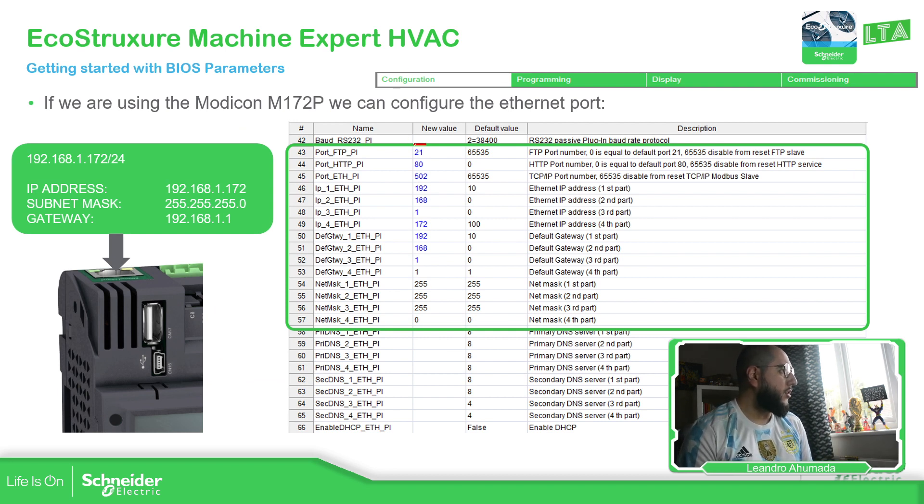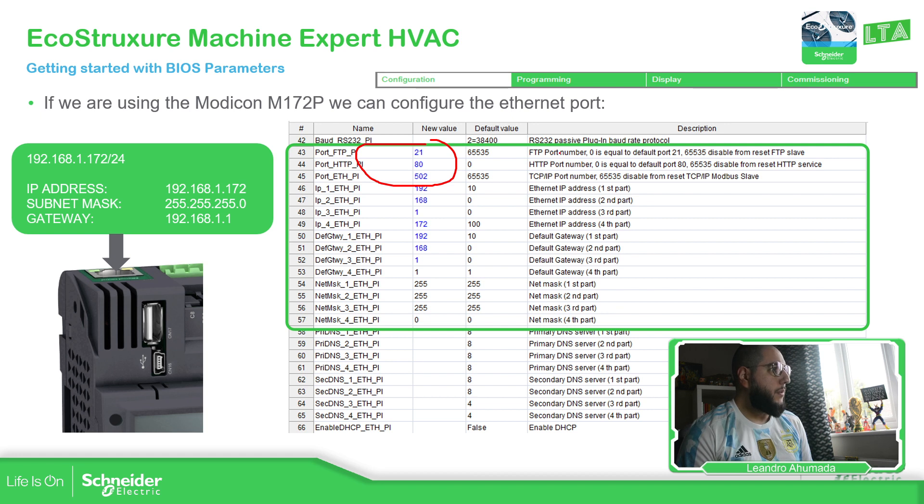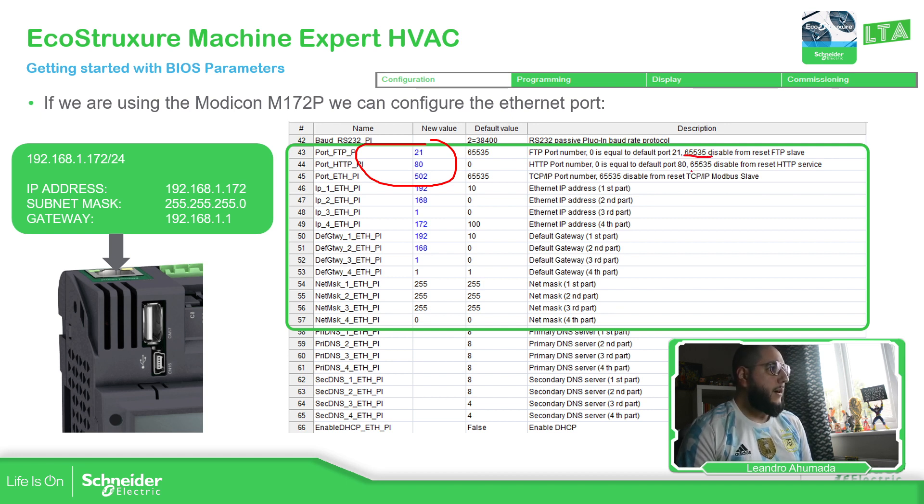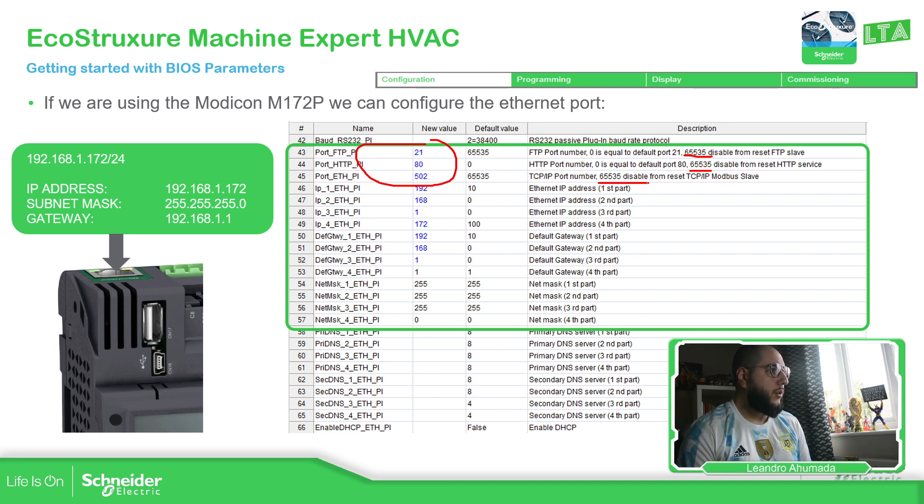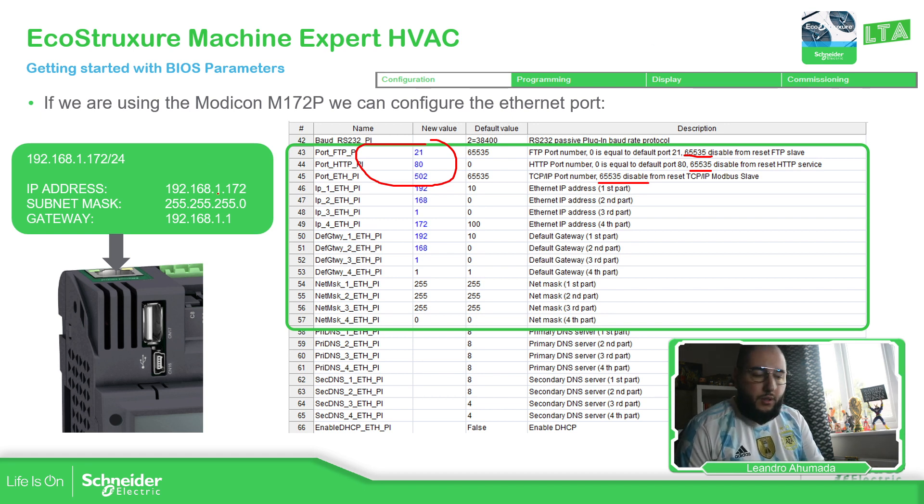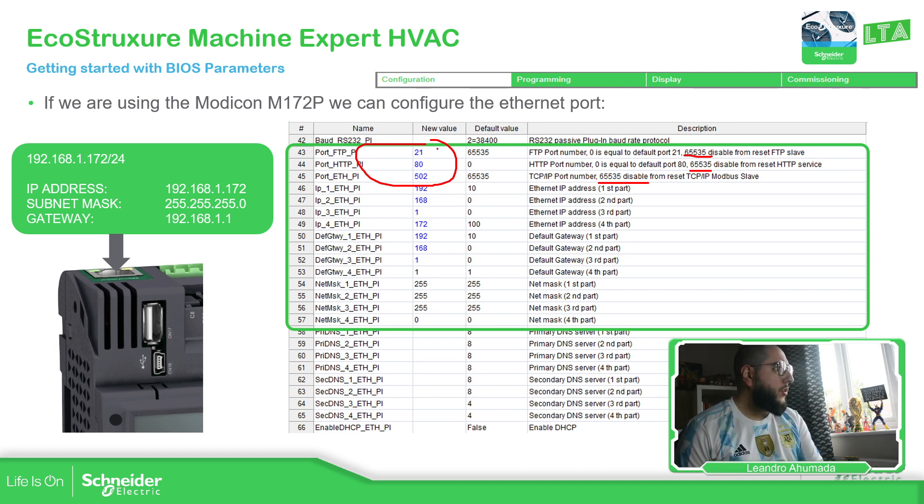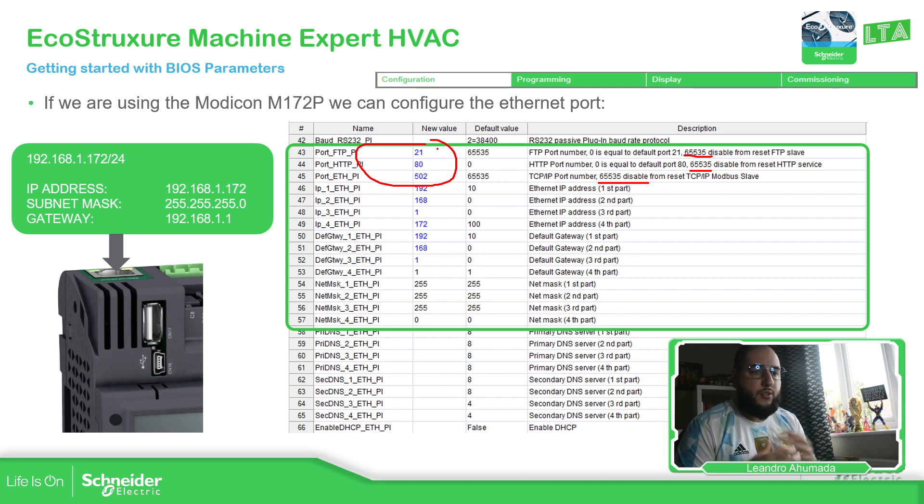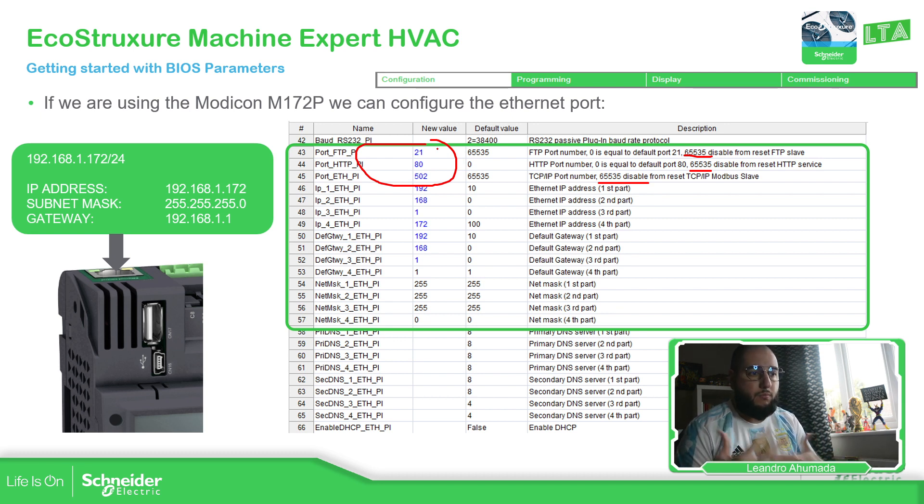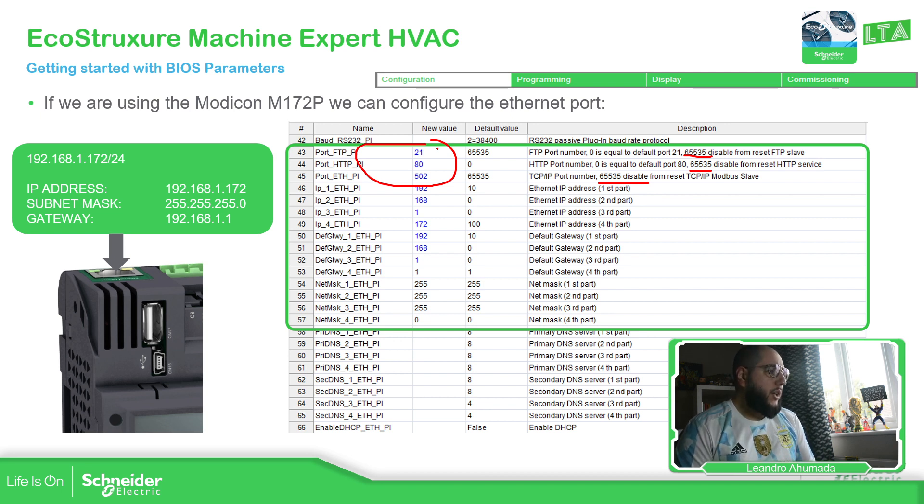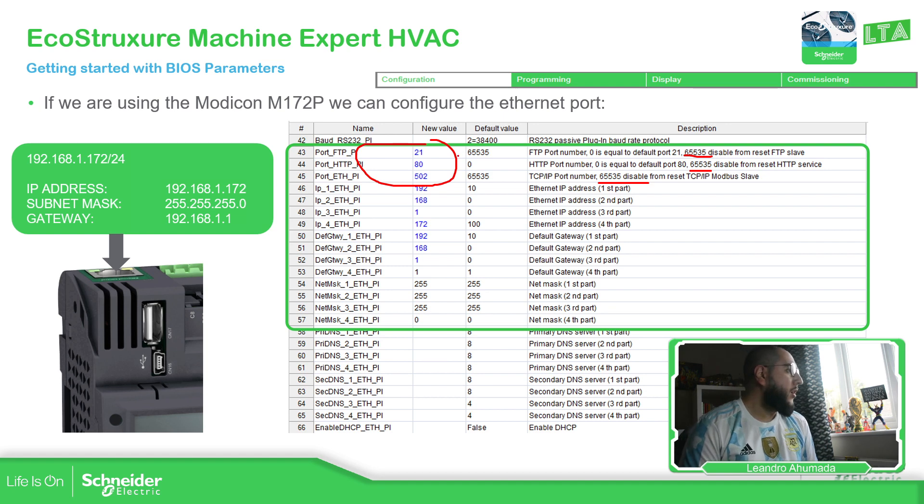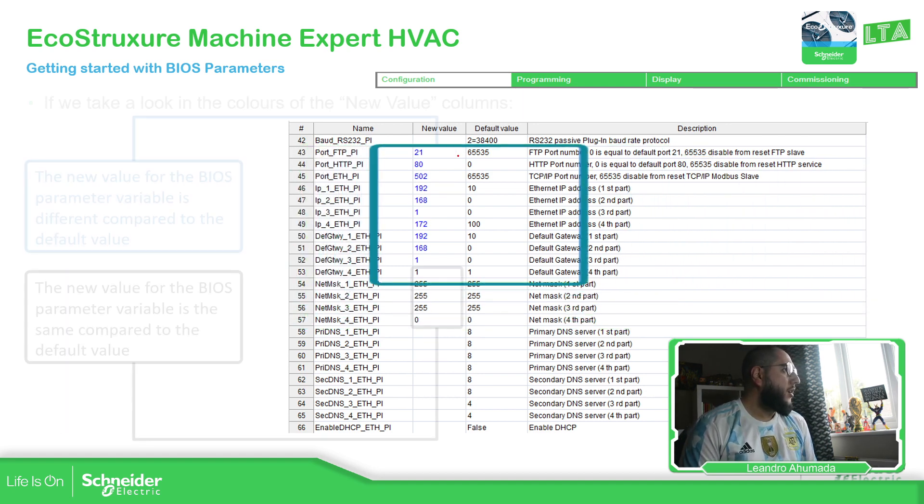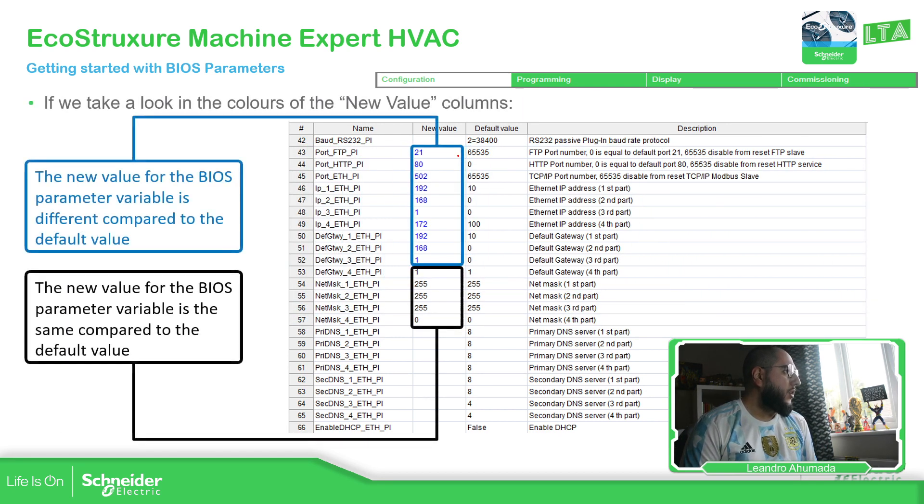Then here is the setting for the ethernet port. Also important, the ports. You have for the FTP, by default is disabled by this number. And here you also have default port HTTP. If you want, you can disable using this number. And in this case for the TCP port, this one is disabled. So this is something important because probably if you're trying to access externally to this controller, probably you have something blocked in there and you're not able to get access. So checking this is important.